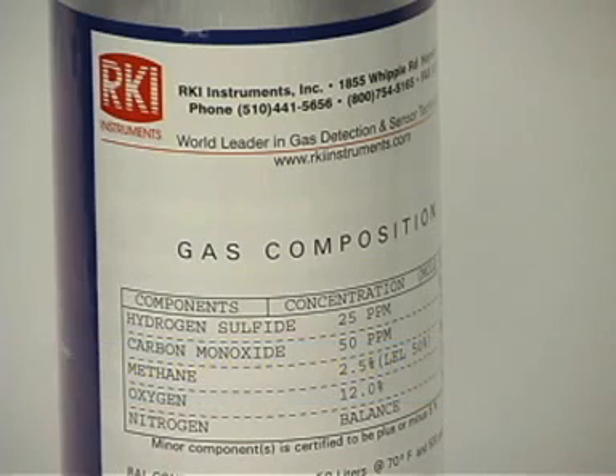To calibrate an Eagle, you will need a known calibration sample of the appropriate combustible or toxic gases. These samples should have concentrations in approximately the middle of the range of detection. RKI offers a 4-in-1 calibration gas cylinder to automatically adjust all of the sensors at the same time for the standard 4-gas Eagle.